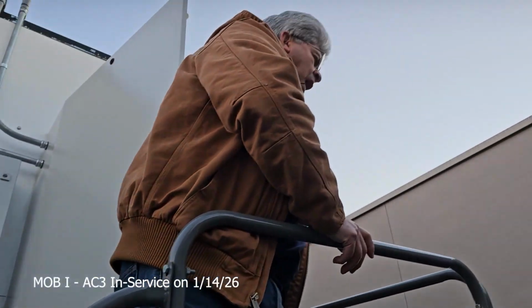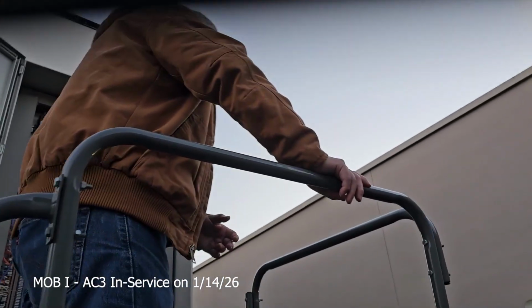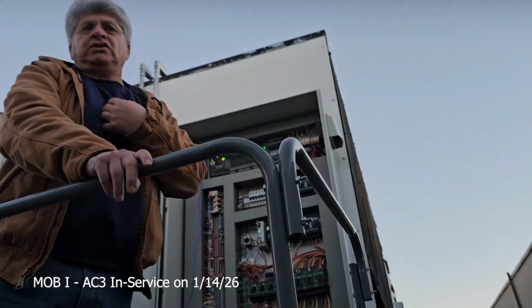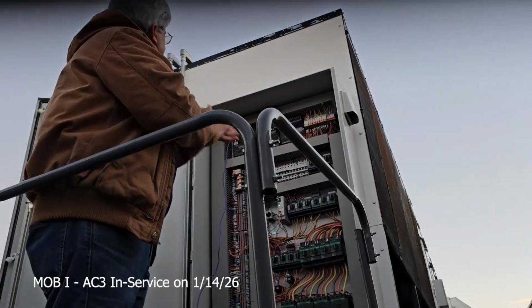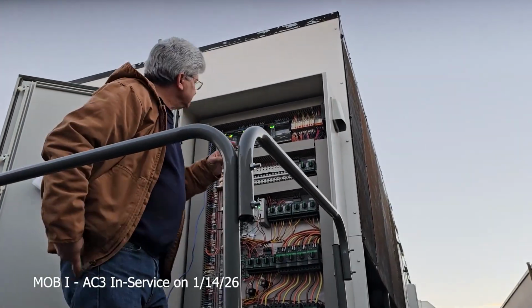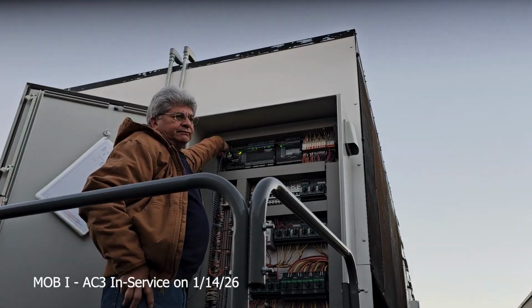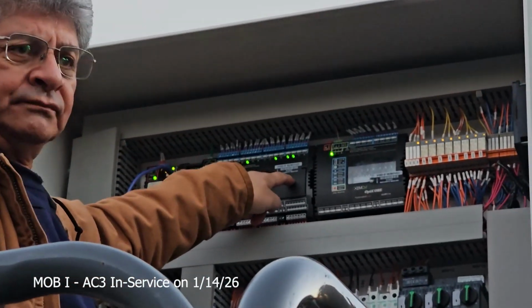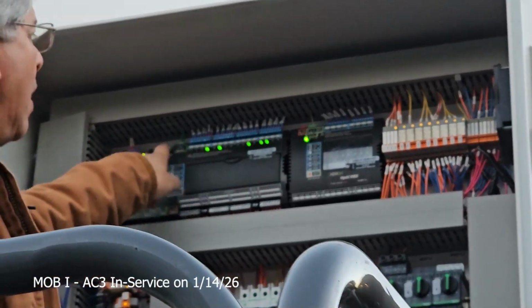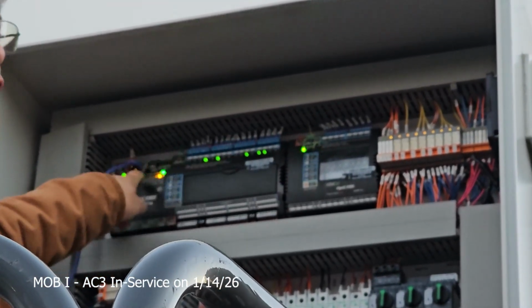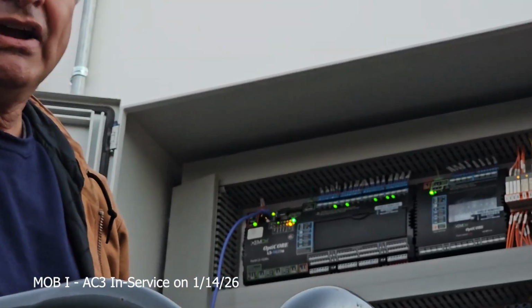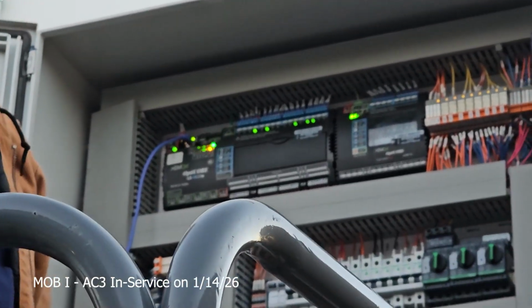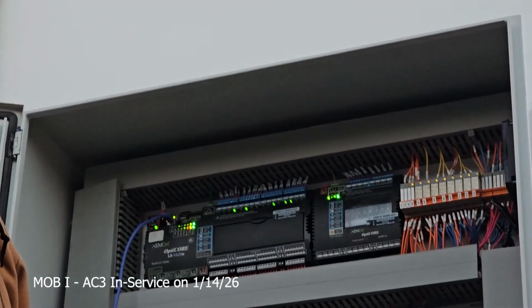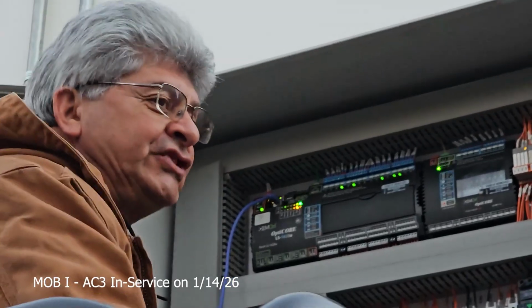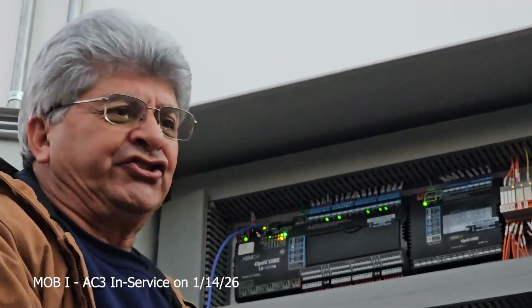So if you guys wanted to turn the equipment off, Vireo might have another procedure that they may want you to use. The way we shut the equipment down, there's a little switch, the power switch right up here. That'll shut power off to this controller. So all the lights will go off. These lights will still stay on. These will all go off. That kills your control circuit for your condenser section only. So you can't go inside the unit now and do work. Your fans are still live.